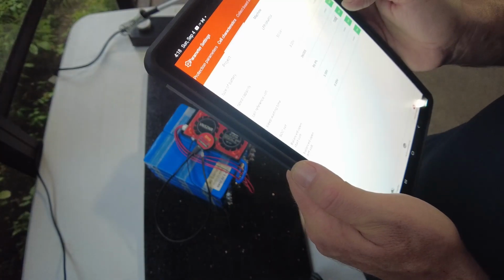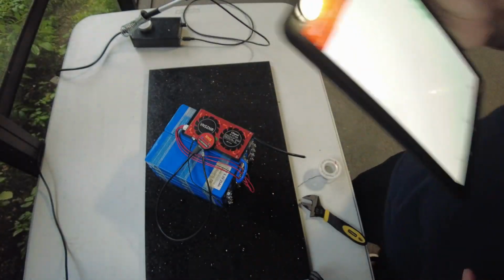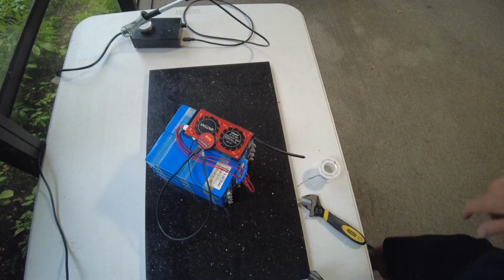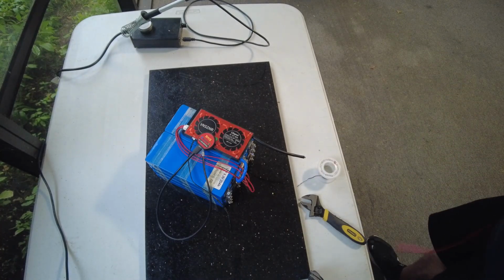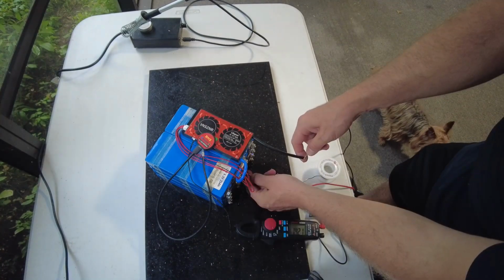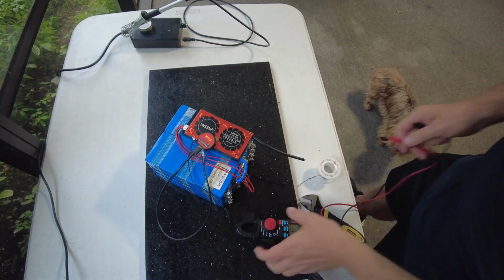If you can see this SOC set, it says 86, so we're going to set that to 100 because we got it top balanced. It's fully charged. Yep, there we go, set to 100 now. Right on. And if we check the voltage, 14.21, all is well.